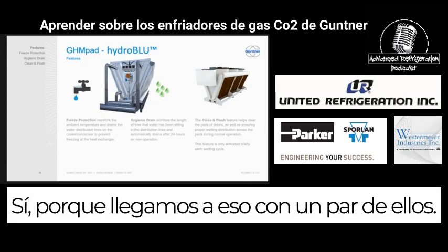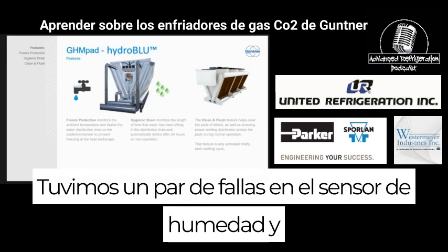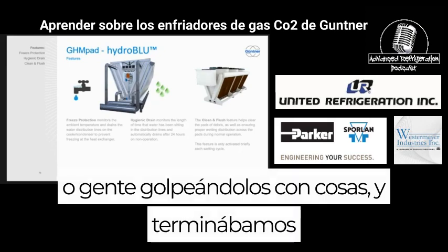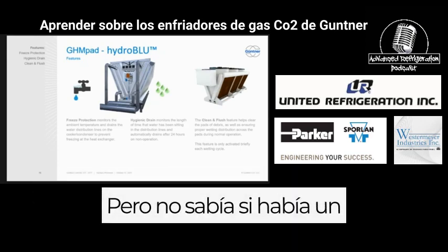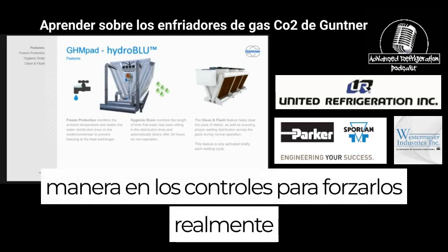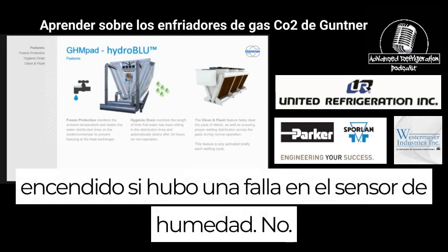Yeah, because we ran into that with a couple of them. We had a couple of humidity sensor failures and/or people hitting them with things, and we ended up having to do the exact thing. We ended up having to override in the Belimo, but I didn't know if there was a way in the controls to actually force them on if there was a humidity sensor failure.